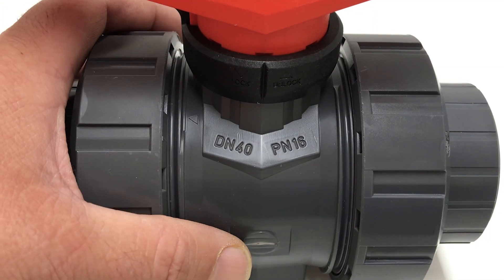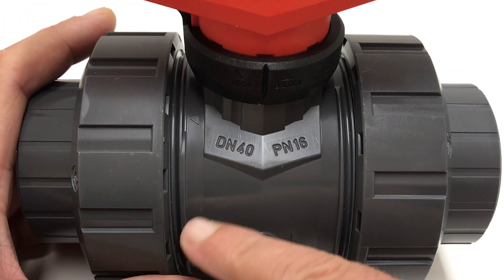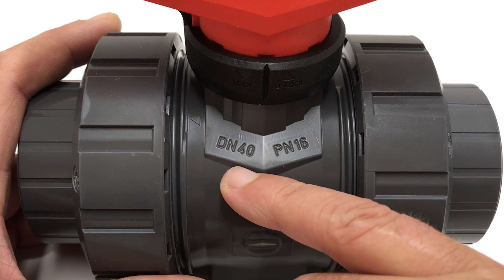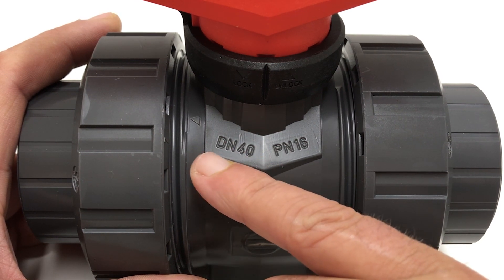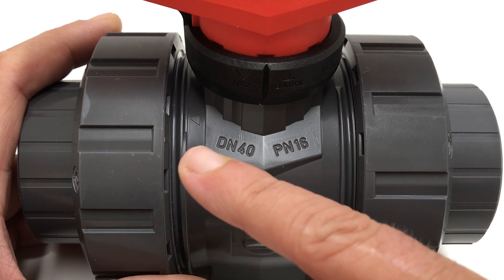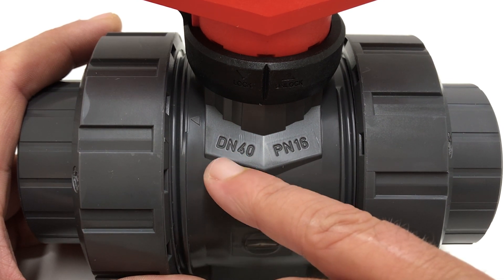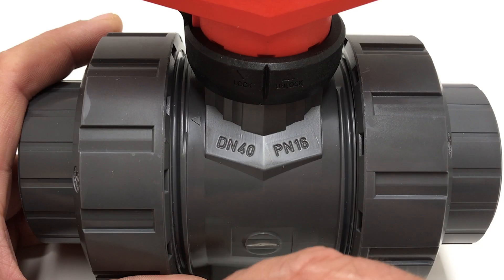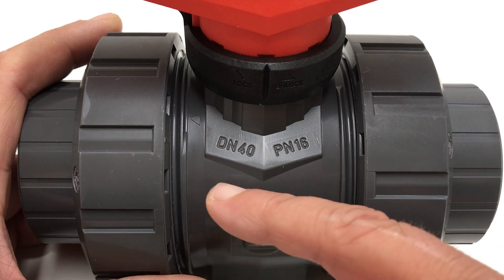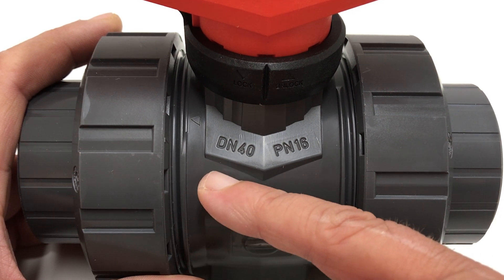Now this is the DN number — we can see that this valve is designated DN 40. This does not simply mean that it is for use with pipe with an outer diameter of 40 millimeters. DN stands for 'diamètre nominal', which is French but translates to English as 'nominal diameter'. But always remember: this is not an accurate reflection of the pipe's outer diameter.